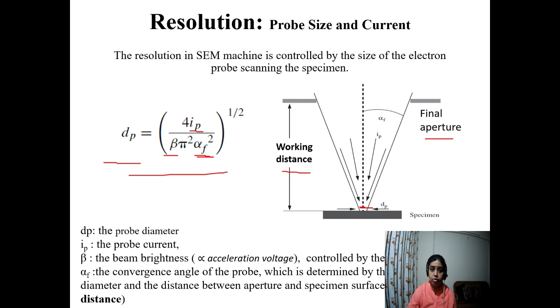Again, one more important parameter is alpha f, the convergence angle. What is a convergence angle? It is determined by the final aperture and the working distance. This is very important: working distance and final aperture. In order to get better resolution, we have to control our probe diameter. So to get high resolution, we have to minimize the probe size. How can we minimize the probe size? Just by increasing brightness and alpha f.